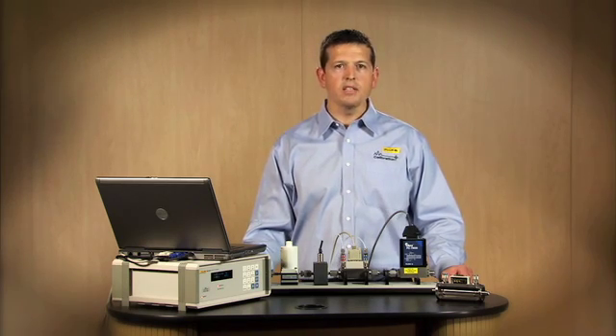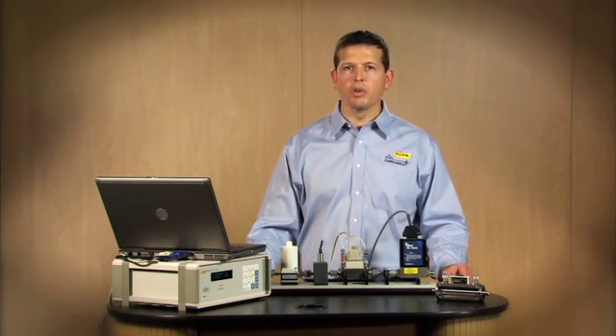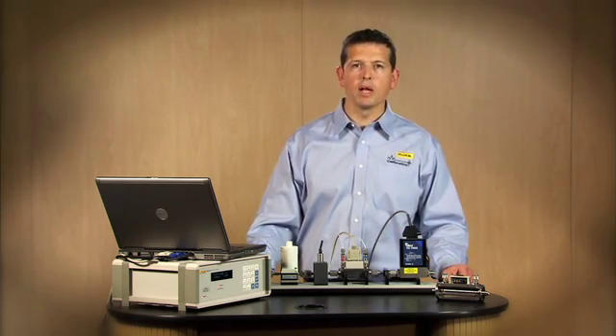The MFC I have today uses a zero to five volt control and output signal which through this cable is controlled and read both by the MFC control option of the Molbox terminal.